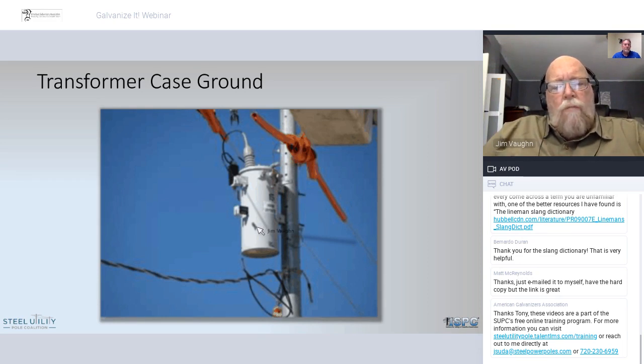There should also be, and it may be on the other side, a ground connection from this connection here over to the pole. In this case, this is a very important connection that occurs here, and here's why. This is the primary lead for the transformer. So this is going to be a 7,200 volt lead that goes into a coil in the tank, and the other end of that coil is connected to this tank on the other side of that lug right there.